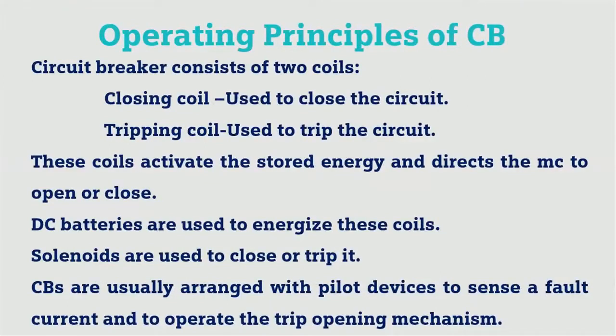When the fixed and moving contacts break, the arc is quenched by the medium — that is the operating principle of the circuit breaker. There are two coils used: a closing coil for closing the circuit and a tripping coil for tripping the circuit. These coils activate the stored energy and direct the moving contact to open or close. DC batteries are used to energize these coils.